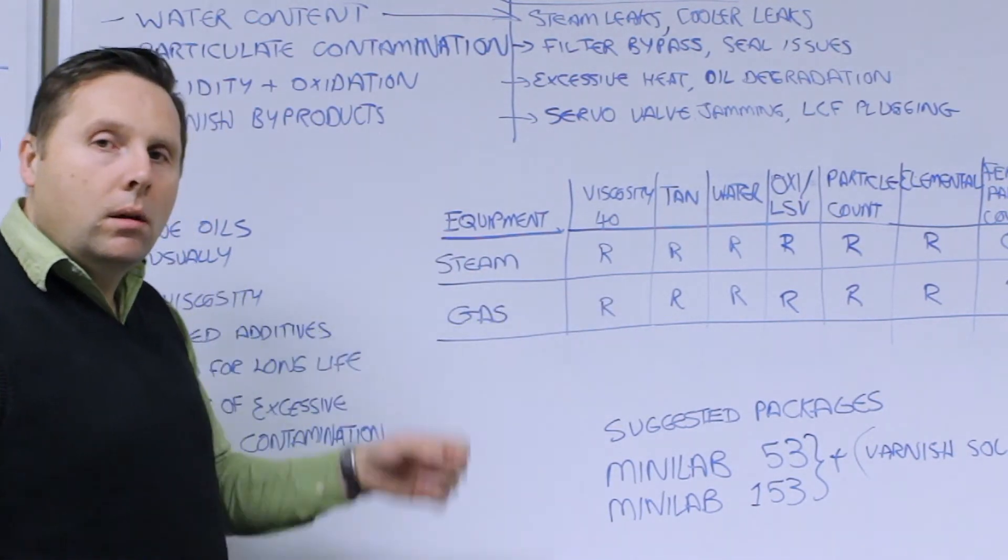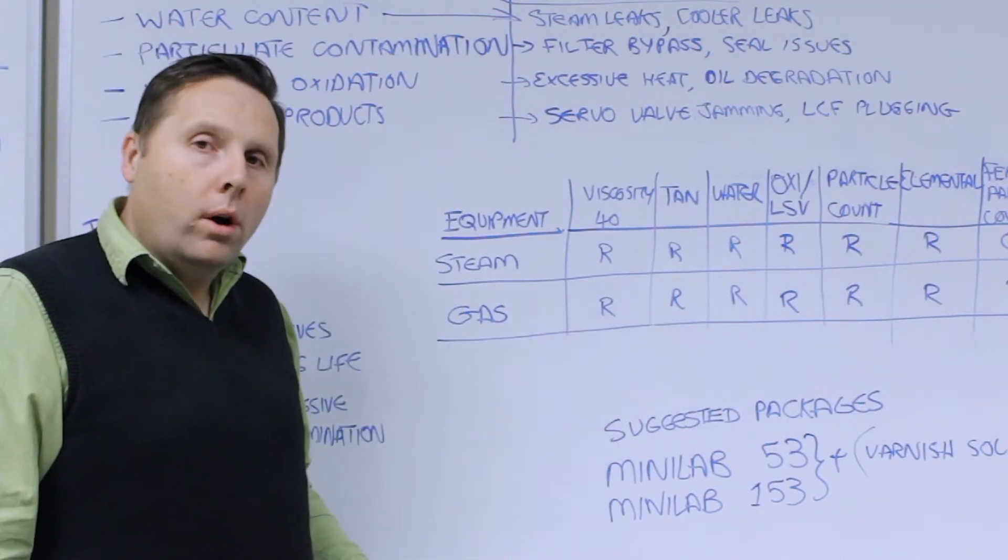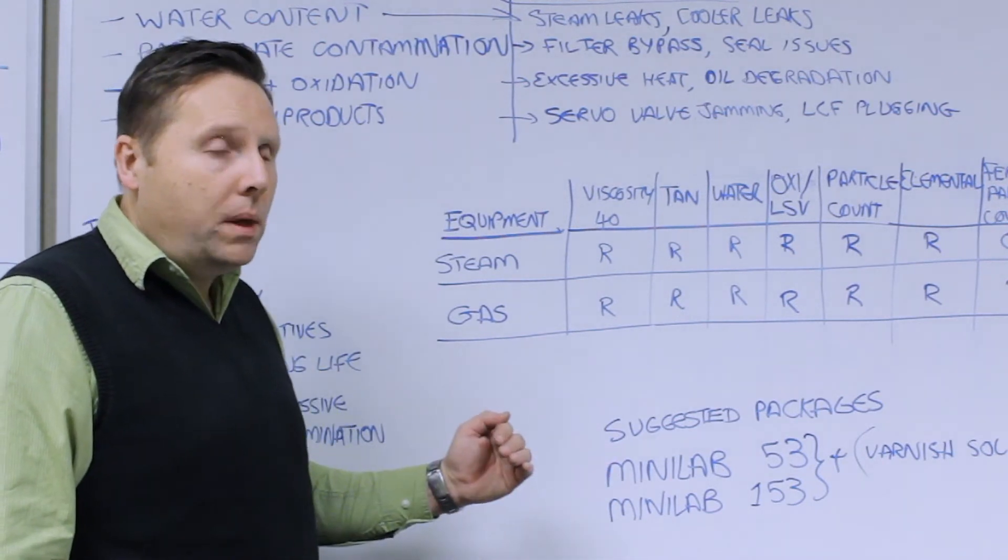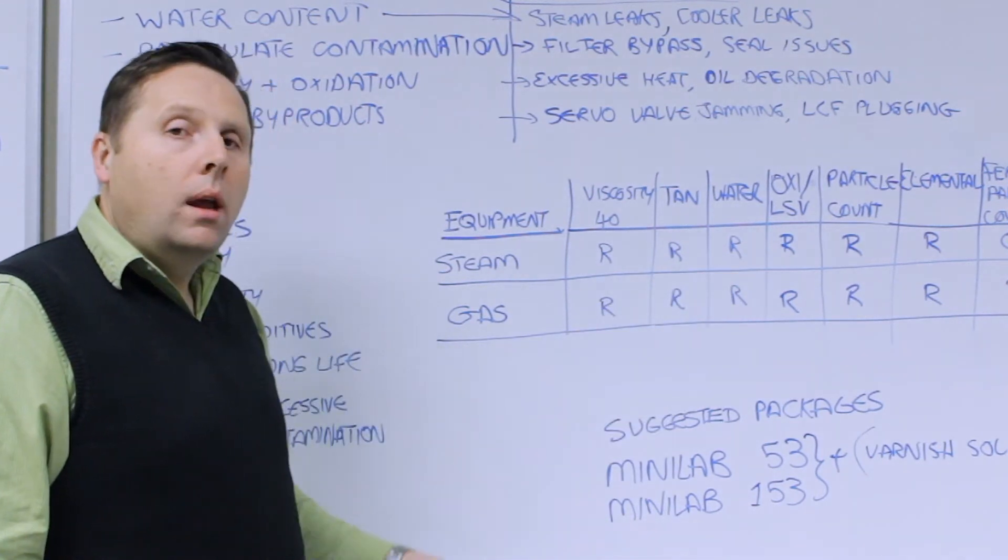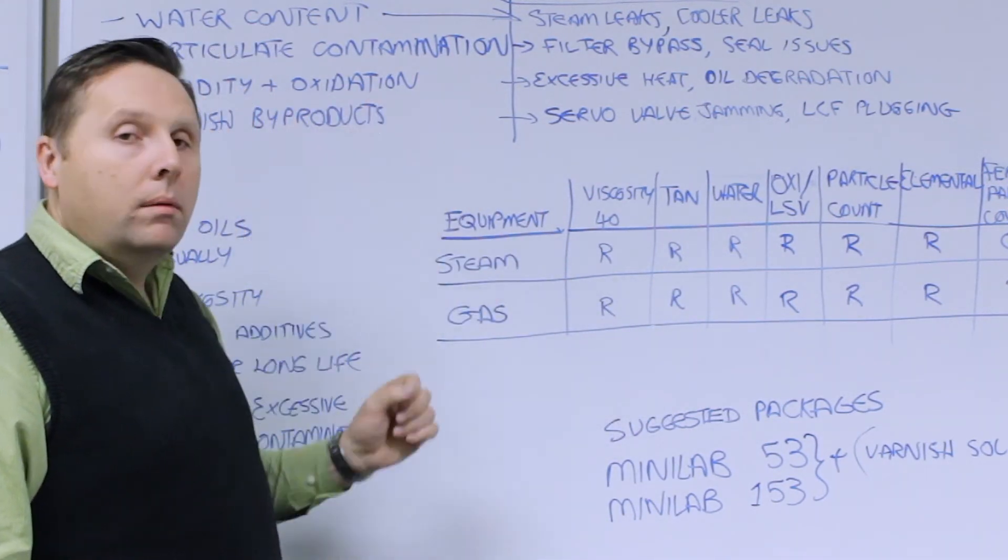We want to look at total acid number. It's indicative of the overall oxidation levels. We want to look at water content, usually low amounts of water for steam turbines. It's 100 ppm is the maximum limit. We want to look at oxidation. That's indicative of lubricant byproducts.